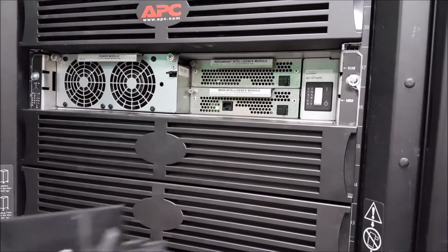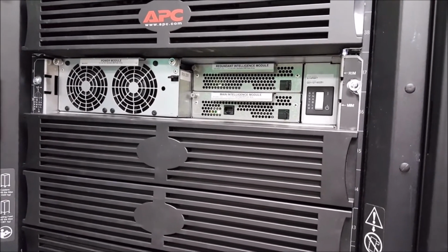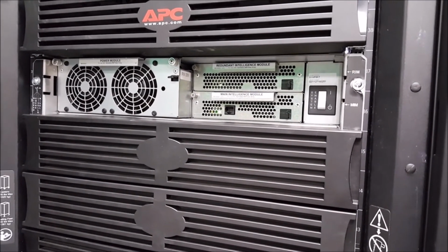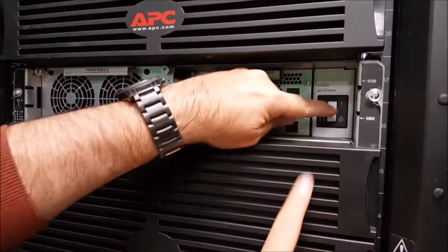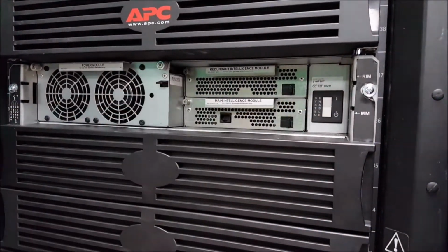The reason for getting this out of the way is so that you can access the system enable switch on the front of the Symmetra RM unit. The system enable switch on the Symmetra RM UPS is to the right of the intelligence modules. Flip it to off and that will begin to power down the UPS.